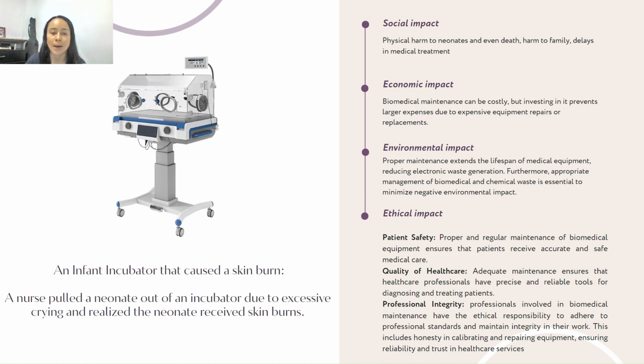In this situation, the biomedical engineer who maintained this medical device had questionable ethics because the safety was bypassed, or through negligence, and his prior preventive maintenance results state he tested and passed the over temperature safety circuit numerous times. An ethical engineer will never bypass a safety circuit and falsify preventive maintenance results. It can be seen in this case that a good job has not been done in the maintenance and calibration of the equipment.